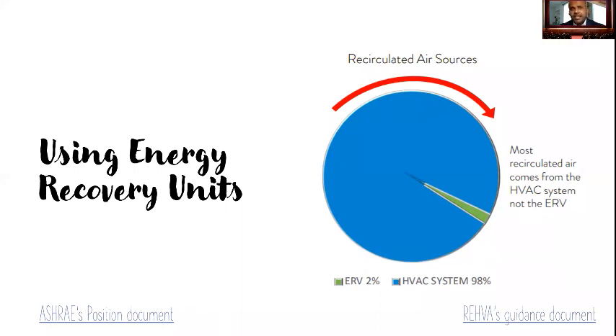If your home or office building has a heat recovery ventilator, an ERV or HRV, keep it running. In well-designed commercial buildings, ASHRAE recommends running the ERVs. With recirculation, however, there's a concern of contamination from the energy wheel. Recirculated air from the wheel or the plate is a fraction of the total recirculation air, as you can see from the graph here. And if you have an ERV, make sure to clean and maintain your energy recovery wheel.